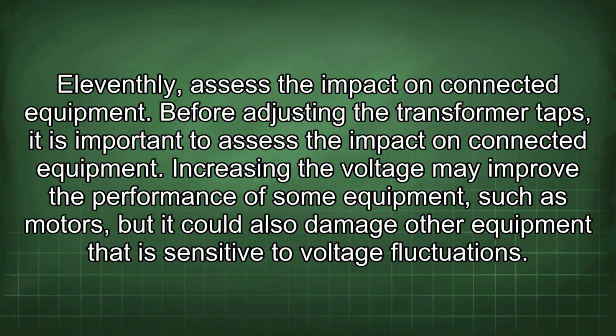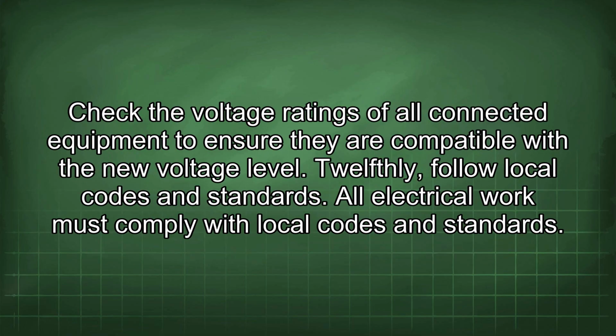Eleventhly, assess the impact on connected equipment. Before adjusting the transformer taps, it is important to assess the impact on connected equipment. Increasing the voltage may improve the performance of some equipment, such as motors, but it could also damage other equipment that is sensitive to voltage fluctuations. Check the voltage ratings of all connected equipment to ensure they are compatible with the new voltage level.